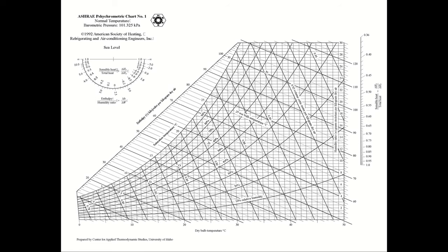So we are through one half of what I want us to do. We went through and determined all of these psychrometric properties using the calculations themselves. The calculations are accurate. They will produce good numbers, even though there are a couple of minor approximations in the process. But if we are okay with even more approximation, we can use the psychrometric chart. The psychrometric chart is a plot of psychrometric properties for a given pressure. It is primarily a plot of humidity ratio versus dry bulb temperature. And again, each psychrometric chart is only good for one pressure. This particular chart is generated at one atmosphere, which is 101.325 kilopascals, which is 1.01325 bar.